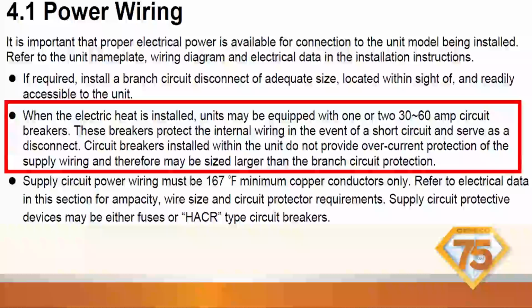We get electricians calling sometimes saying, you guys already have breakers in there. I'm like, yeah, but that's not sized for your wire. Your wire is sized according to the amperage of the heat strips, and the overcurrent protection, if it's going to trip the breaker, is at the panel. So again, that's important to know. Supply circuit power wiring must be rated 167 degrees minimum, copper conductors only. Of course, refer to the NEC code book for ampacity, wire size, and circuit protector requirements.